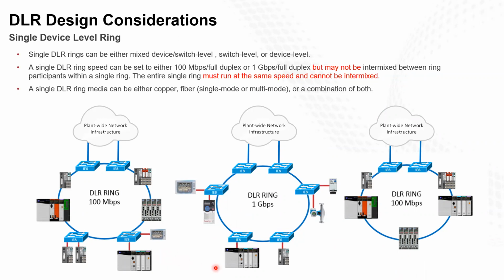If you're going to be using fiber, and especially single mode, you're going to have to use our switches that currently have ring members, or our Flex 5000 now has a communications device, a COM card, which will accept SFPs. So we'll use that. Those will be direct ways of supporting a 1 gig Ethernet.